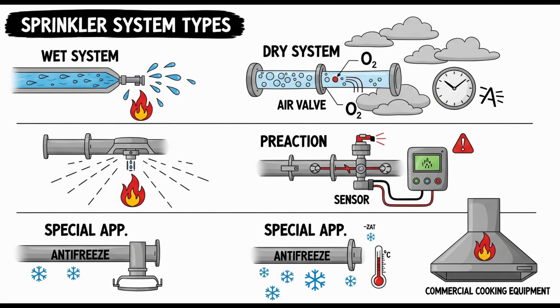Let's completely shift gears now to a very different but equally specific and challenging hazard: commercial type cooking equipment and the associated ventilation systems. We're talking restaurant kitchens and grease fires. Yes, another distinct and high-risk fire hazard area. The standard requires that in cooking areas already protected by general automatic sprinklers, meaning standard overhead sprinklers installed in the room, additional, specifically targeted sprinklers or automatic spray nozzles are needed to protect the commercial cooking equipment itself, like fryers, griddles, broilers, and the associated ventilation systems, the hoods and ducts that carry grease-laden vapors. This additional protection is necessary, unless that equipment and ventilation system are already protected by another approved method, typically a listed dedicated fire extinguishing system.